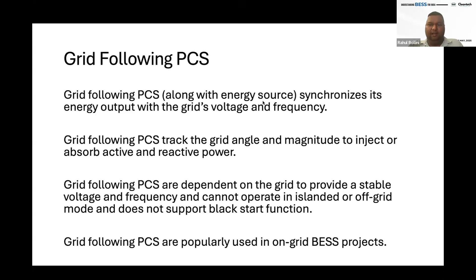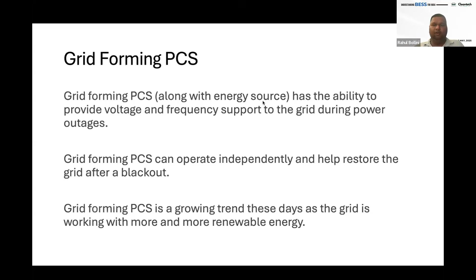The new type of PCS that many countries are newly adopting is called grid-forming. Grid-forming works along with the grid, and when the grid does not work, it can support a blackout. Typically the functions include black start as well as handling a power outage. This is very helpful for off-grid projects, especially when trying to have an independent grid, and also for on-grid projects in places that don't have a reliable power system. So grid-forming PCS is useful there.